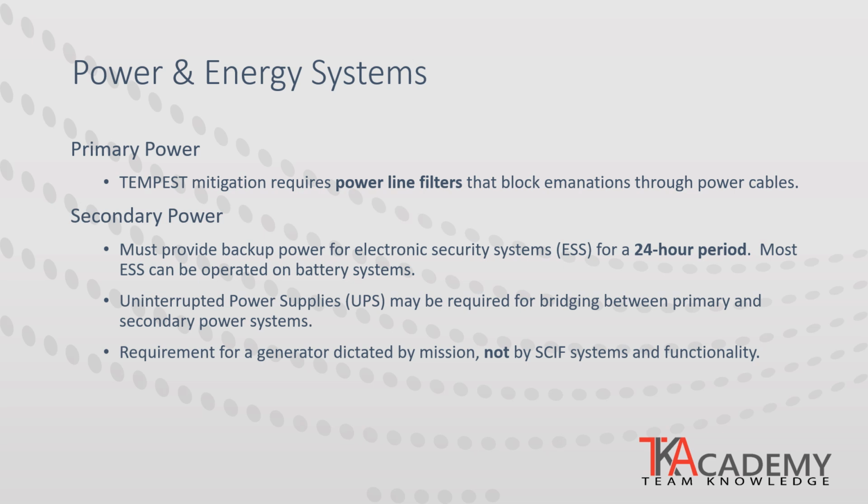Most SCIFs handle, process, and store information digitally and cannot risk the potential of losing data when power is lost, so uninterruptible power supplies, or UPSs, are often provided to bridge between the primary and secondary power systems. It is common for emergency generators to be associated with SCIFs, but a SCIF does not require a generator. It is the mission that dictates the requirement of a generator, not the facility.